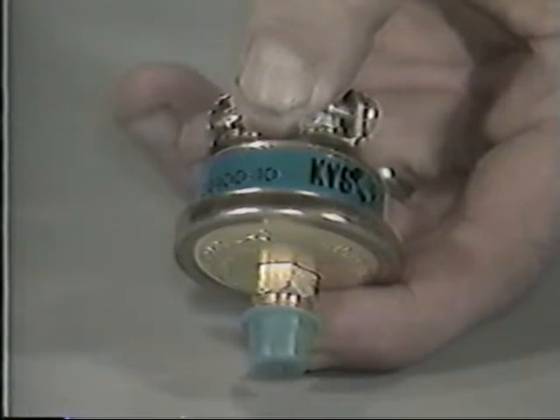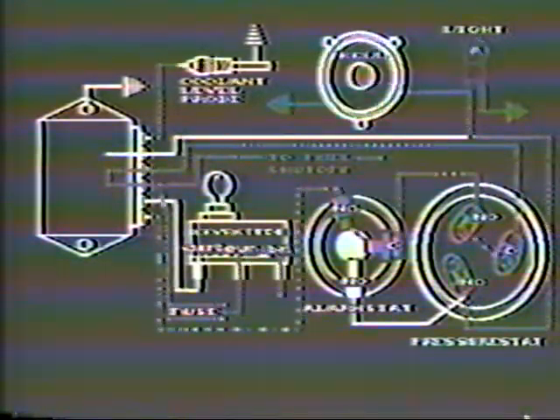Let's examine system behavior in the event of an engine problem, starting with oil pressure. The system we've been looking at has a -10 pressure stat. That means it will alarm at 15 pounds and shut down at 10 pounds. If oil pressure falls, the pressure stat NC switch will close at 15 pounds, giving voltage to the light and bell and causing a low oil pressure alarm. This is no different than what we saw with 9033 and 9032.